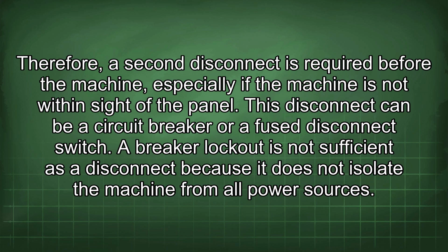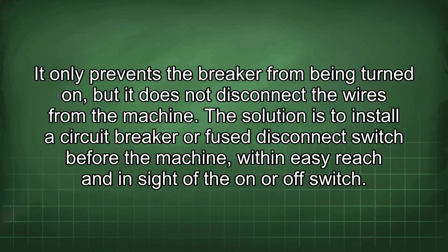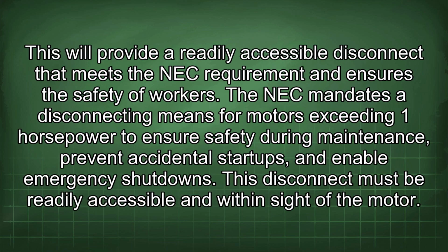A breaker lockout is not sufficient as a disconnect because it does not isolate the machine from all power sources. It only prevents the breaker from being turned on, but it does not disconnect the wires from the machine. The solution is to install a circuit breaker or fused disconnect switch before the machine, within easy reach and in sight of the on or off switch. This will provide a readily accessible disconnect that meets the NEC requirement and ensures the safety of workers.